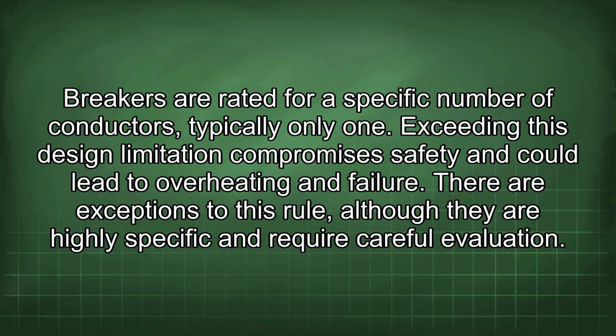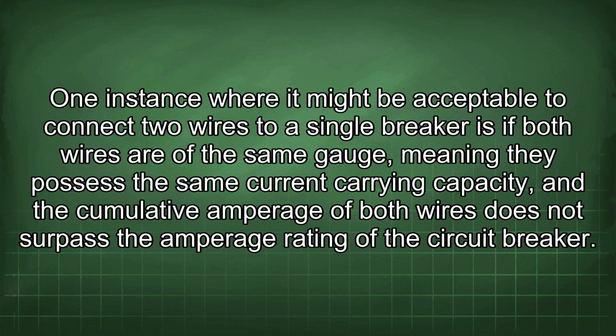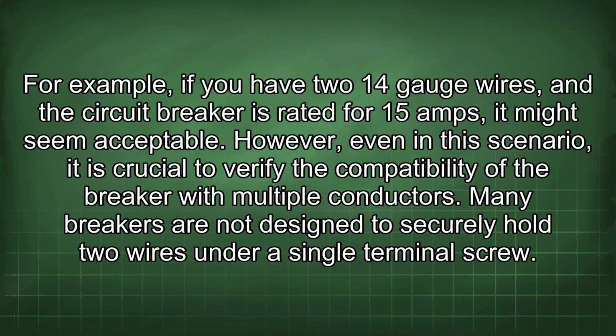There are exceptions to this rule, although they are highly specific and require careful evaluation. One instance where it might be acceptable to connect two wires to a single breaker is if both wires are of the same gauge, meaning they possess the same current carrying capacity, and the cumulative amperage of both wires does not surpass the amperage rating of the circuit breaker. For example, if you have two 14-gauge wires, and the circuit breaker is rated for 15 amps, it might seem acceptable. However, even in this scenario, it is crucial to verify the compatibility of the breaker with multiple conductors.